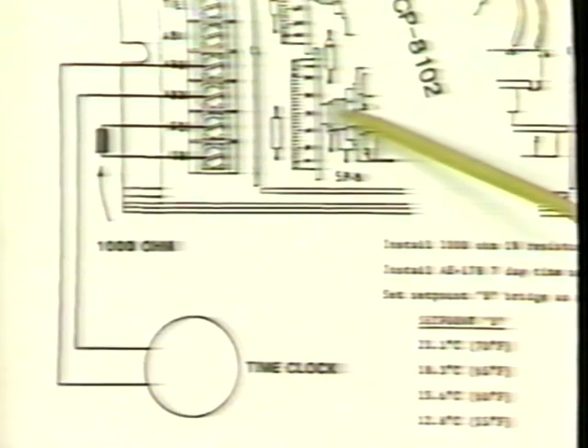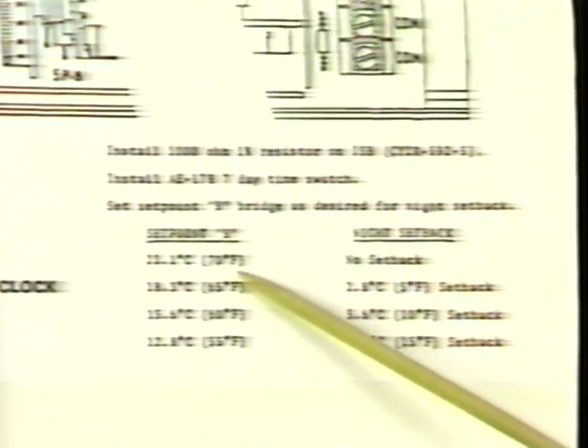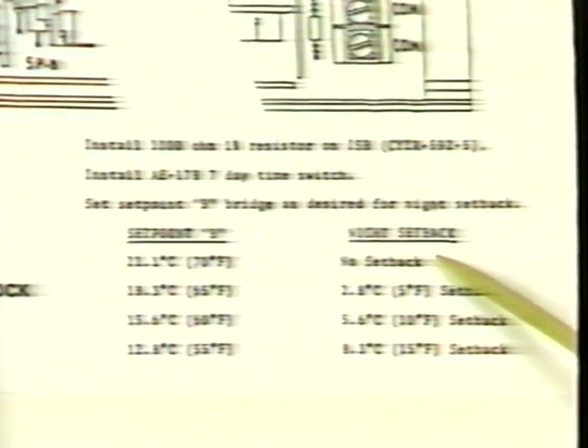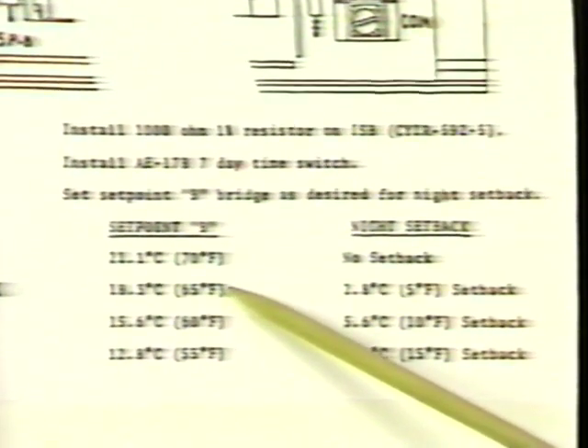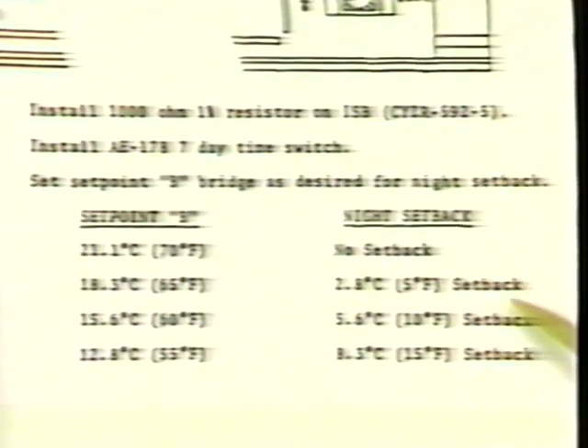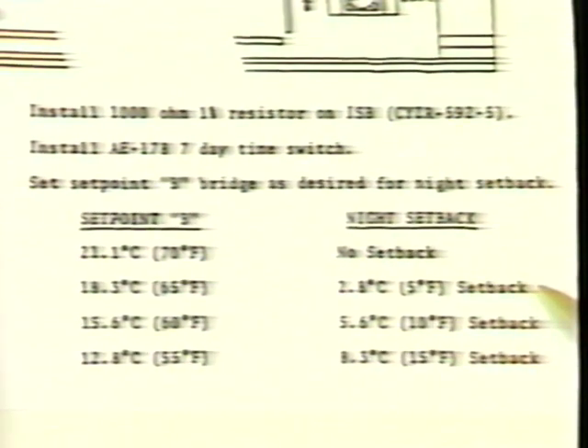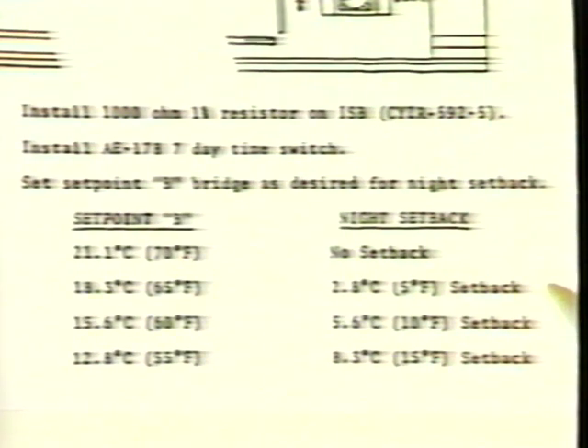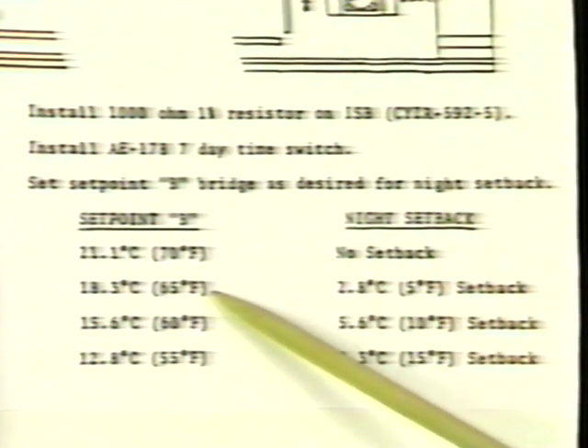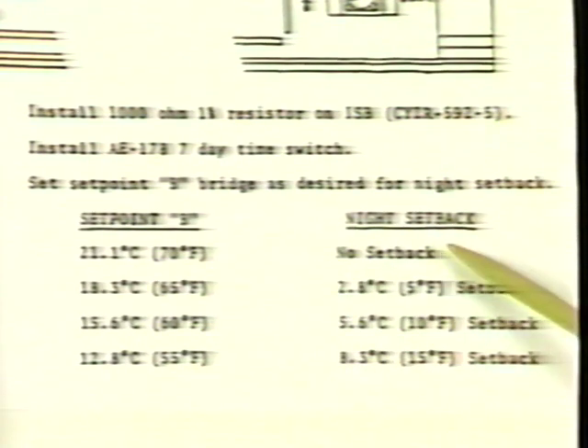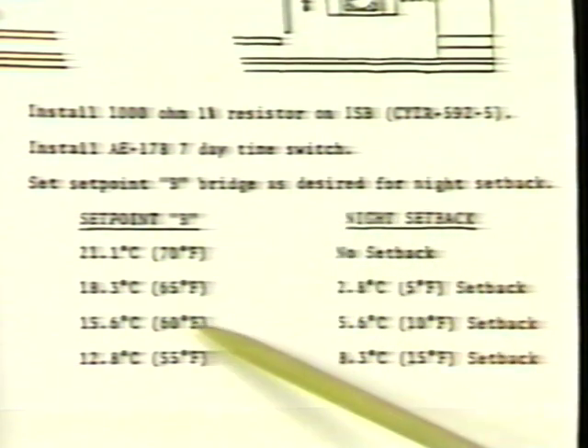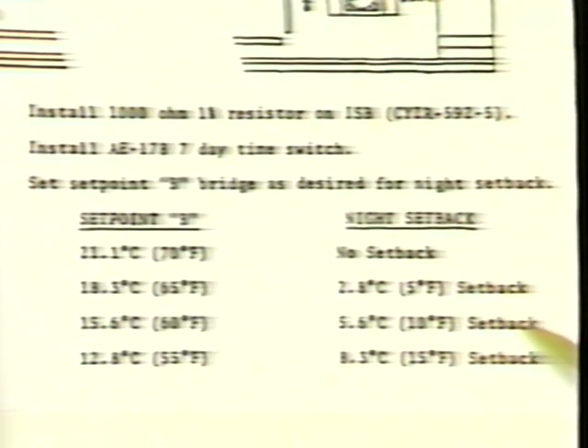The amount of setback will be determined by the setting on set point B as follows. When set point B is set at 70 degrees, there will be no setback. However, if we move it down to 65, that will create a 5-degree setback in whatever the controller set point is. For example, if the controller set point is 72 degrees, when the time clock is engaged, and if set point B is set at 65, we will get a 5-degree reduction in that set point. The set point will then drop from 72 to 67 degrees. Further reductions in set point B will result in greater setback.